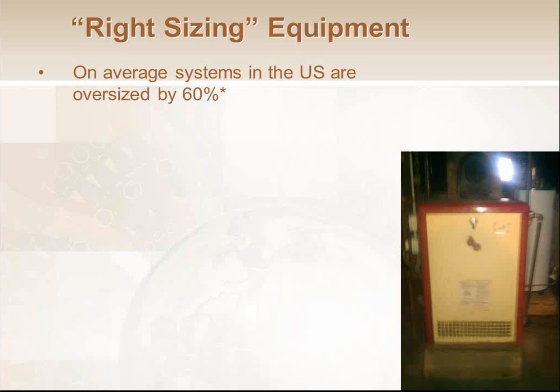Another thing we look at quite a bit, and we teach this in some of our half and full day classes if anybody comes to those, is right-sizing equipment. As you probably realize, most boilers are oversized out in the marketplace. And by most, I mean 100% of the boilers that we have looked at in the past 20-some years. A lot of you know Bill Bailey in our office. He does a lot of our boiler design work, and he helps me teach some of these classes. Pretty much every week he's going out helping people resize boilers, especially this time of year. And in 26, 27 years, he's never once been to a job where he could not downsize the boiler. Literally 100% of the boiler plants are oversized.